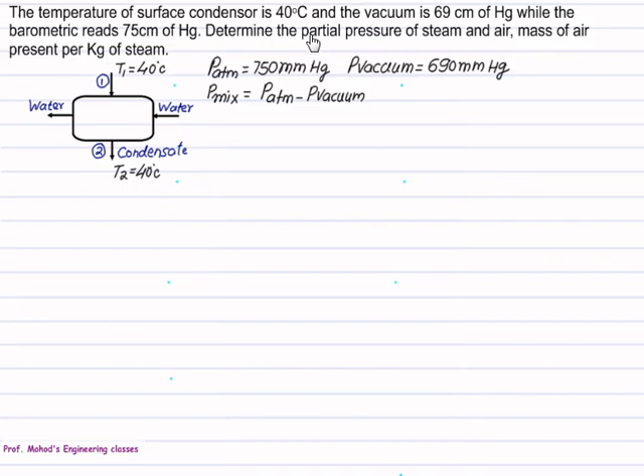The temperature of the condenser is given as 40 degrees Celsius. So we assume T1 equals T2 equals 40 degrees Celsius. The vacuum is given as 69 cm of Hg. Barometer reads 75 cm of Hg. So we can find out P_mix which equals atmospheric minus P_vacuum. To find the partial pressure of steam and air we have to use Dalton's law. Mass of air can be found out using the ideal gas equation.